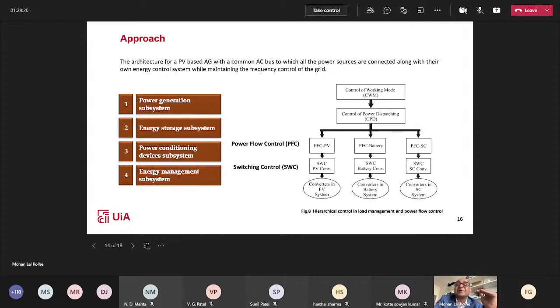So how the power flow and switching control is going to work. The main function of this hierarchical stage is to calculate the reference values for PWM switching controls of VSIs, which is connected with the PV array and the centralized energy storage, based on the control parameters received from the CPD level. So here you have energy storage.